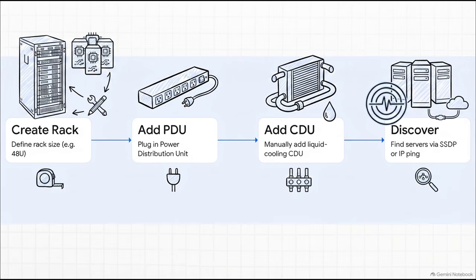First, you create your rack configuration. Then you plug in the PDU, add your liquid cooling CDU manually, and finally, you command the software to discover your shiny new servers. It does this using SSDP or an IP ping spray, which is basically like sending out a digital sonar ping across the network to find your exact hardware and map out the data center automatically.